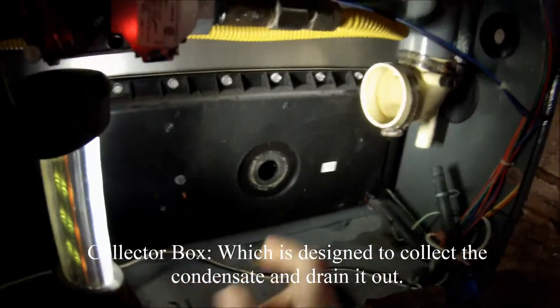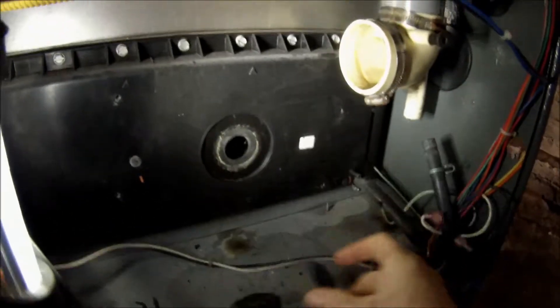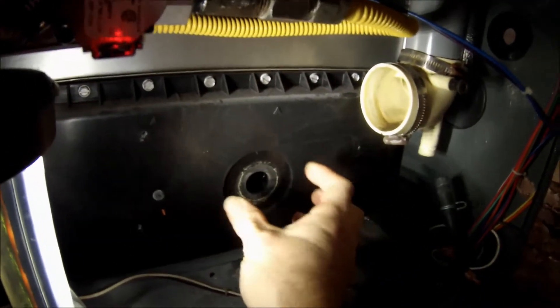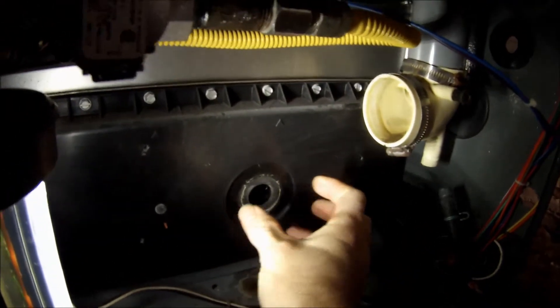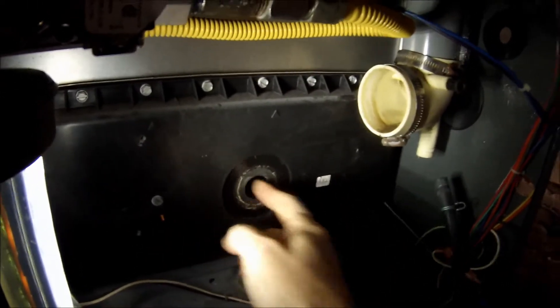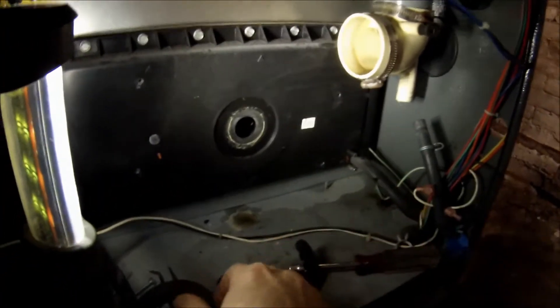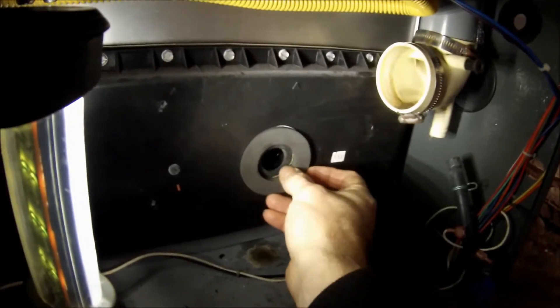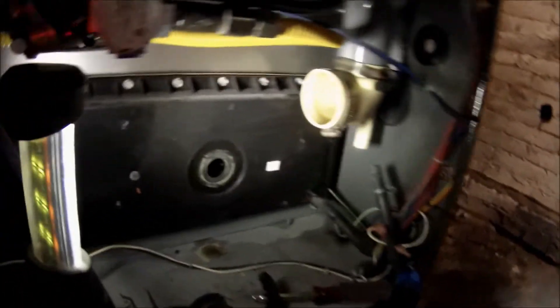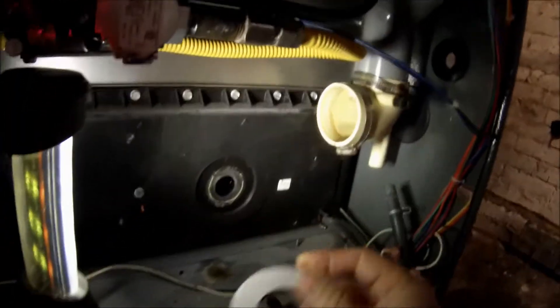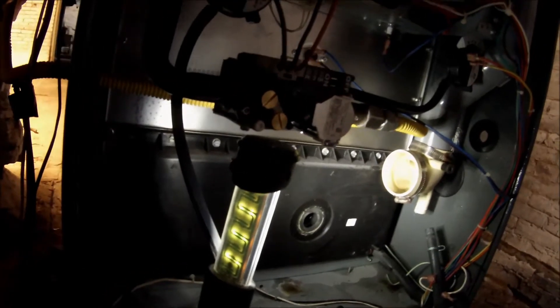So if that seal is bad, it's going to leak air. It's going to be sucking air here, but it's going to suck air from, you know, not from inside as well because this seal is bad. So you must replace this seal. So I took that one off and started to clean here to put my new seal on. So I'm going to do that now. I'm going to show you, I'm going to tell you why this is important in a second here.